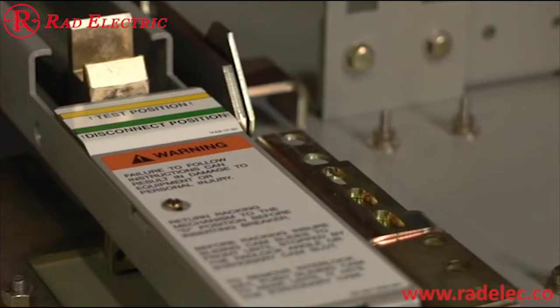Letters on the racking mechanism indicate which position the circuit breaker is in. D means the circuit breaker and the mechanism are in the disconnect position. The other positions are T for test and C for connect. Whether you manually or electrically rack the circuit breaker, the position indicator must be visible through the door. These yellow and green bars line up with the front of the circuit breaker. As the circuit breaker is racked, this block connects with the circuit breaker and moves in and out of the cell.